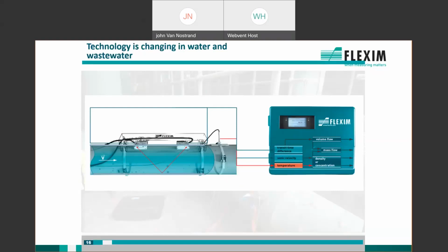One of the unique things that we do is we measure the sound speed of the media when we install a FLEXIM meter. Now we can accurately correlate the sound speed with the water temperature in drinking water distribution systems by calibrating the sound speed to the temperature of the water. This is done by taking a sample of the water and inputting that value into the meter. Once it's calibrated, the meter will accurately report the temperature as it relates to changes in the sound speed. This is unique to FLEXIM because our sound speed measurement capabilities are extremely accurate.